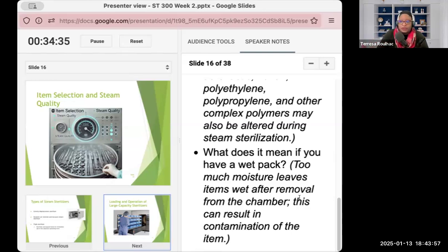So how does this happen? Well, when we open up the autoclave, we let the steam come out. And we usually keep the instruments in there for a good 30 minutes before we pull them out, to let the instruments cool completely. But let's say you pull them out too fast and put them right onto the drying rack without letting them cool all the way. Then moisture builds up in different places, and that's where we get the wet load.